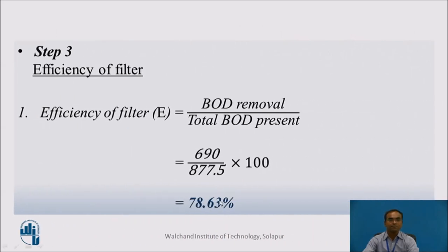Step 3: Calculate filter efficiency. Efficiency E = (BOD removed / BOD applied to filter) × 100 = (690 / 877.5) × 100 = 78.63%.